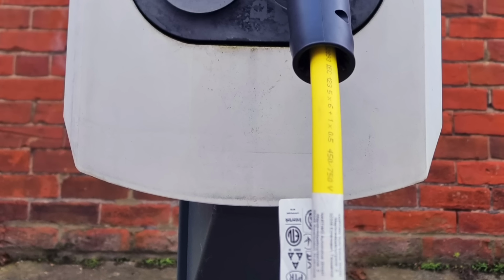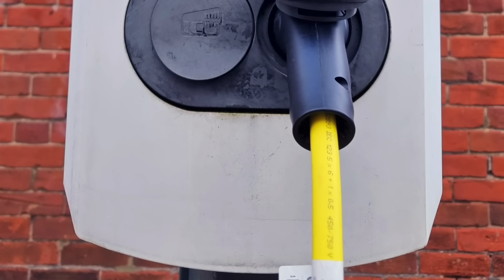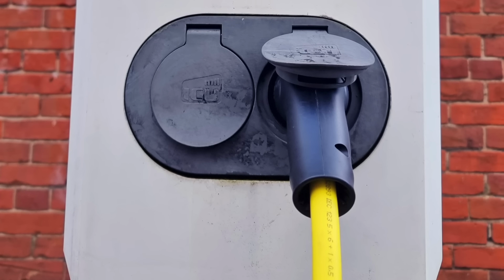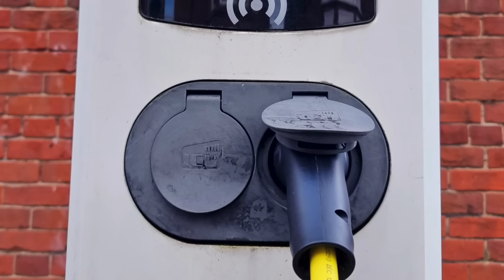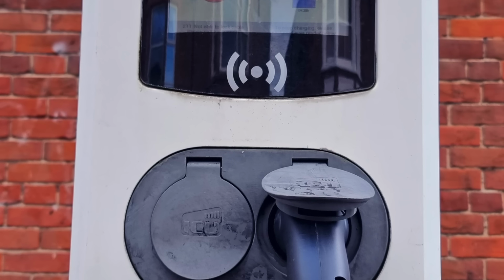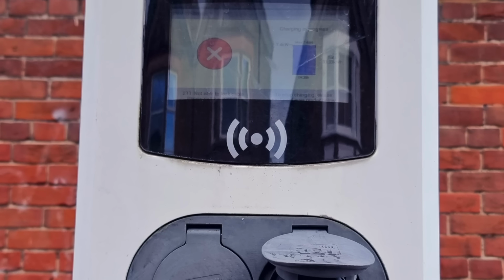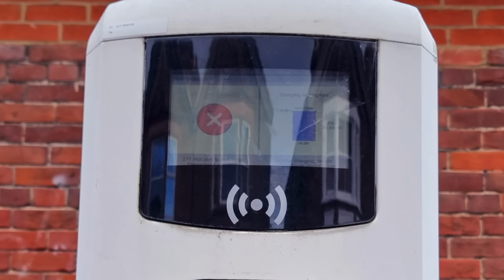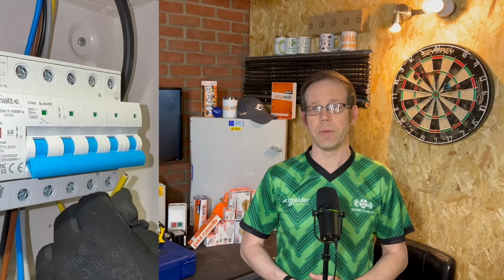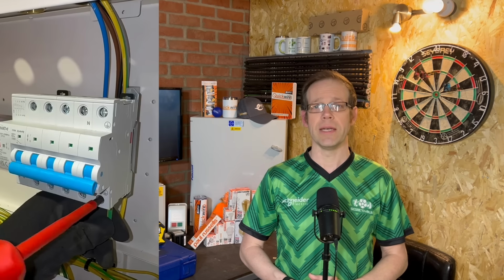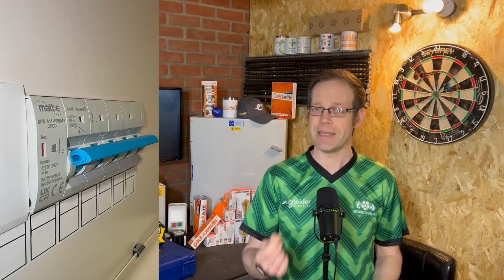Third, consider insulation and other barriers. For instance, you could use non-conductive materials, coatings or enclosures to prevent contact with live metal parts. This is effective as a supplementary control, but it needs durability, inspection and maintenance to ensure it stays robust into the future. Finally, protective devices such as open pen conductor detection devices, or OPDDs, can detect fault conditions and disconnect the supply automatically. They're useful for enabling PME systems, but remember, they only mitigate specific faults.